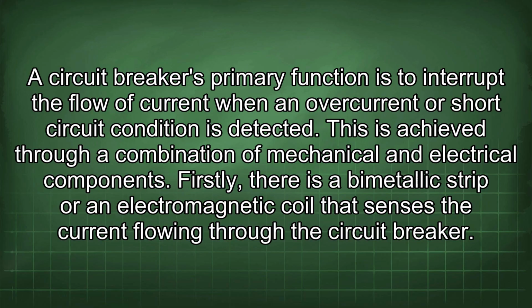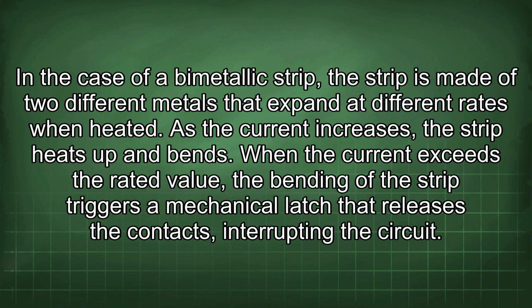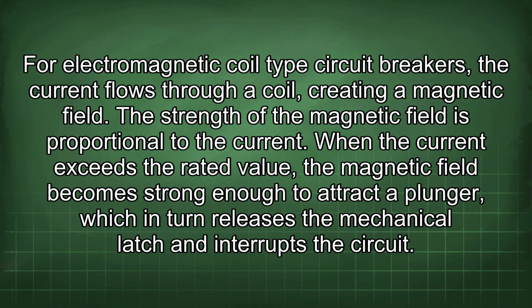Firstly, there is a bimetallic strip or an electromagnetic coil that senses the current flowing through the circuit breaker. In the case of a bimetallic strip, the strip is made of two different metals that expand at different rates when heated. As the current increases, the strip heats up and bends. When the current exceeds the rated value, the bending of the strip triggers a mechanical latch that releases the contacts, interrupting the circuit. For electromagnetic coil-type circuit breakers, the current flows through a coil, creating a magnetic field. The strength of the magnetic field is proportional to the current. When the current exceeds the rated value, the magnetic field becomes strong enough to attract a plunger, which in turn releases the mechanical latch and interrupts the circuit.